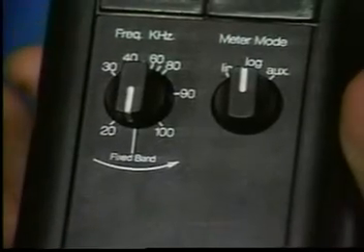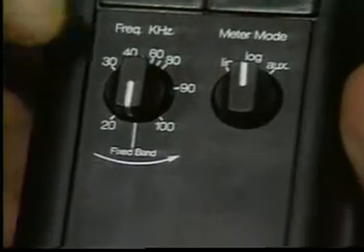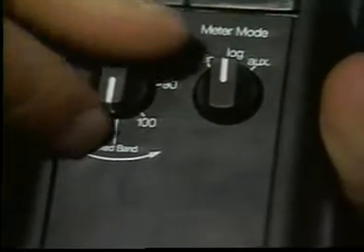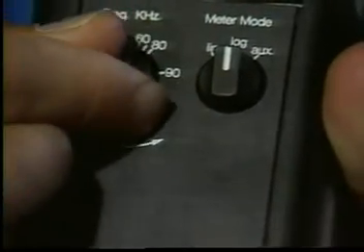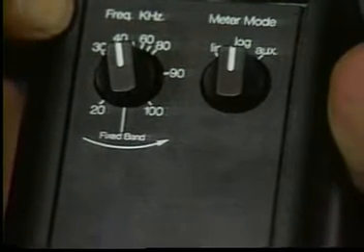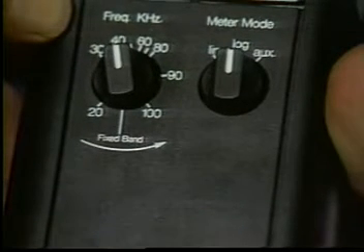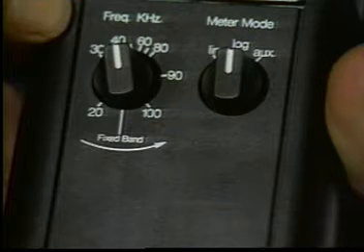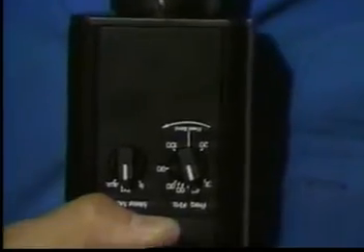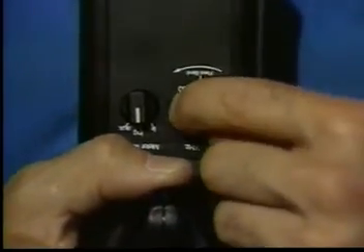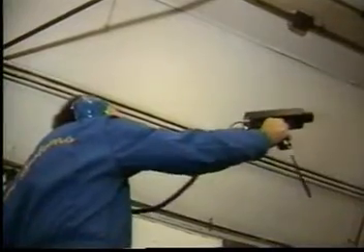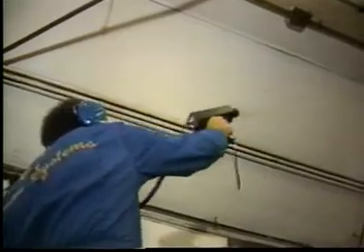You can also try one of the Ultraprobe's advanced features, the tunable frequency filter. Change the frequency tuning on the Ultraprobe to about 40 kilohertz. In order to adjust it to the exact frequency, use this simple method. Sniff while adjusting the frequency until the clearest sound is heard, and continue to scan as previously demonstrated.